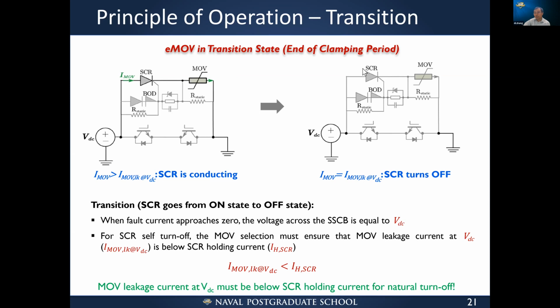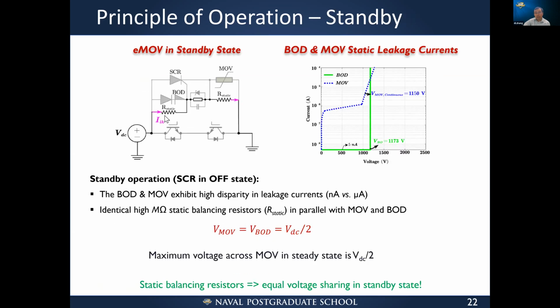So when the thyristor is turned off, the voltage sharing between the thyristors and the MOVs will be determined by the static voltage divider resistance. We just pick the values here so we can control the voltage sharing across the SCR and the MOV. For easy design, we keep it simple, half and half. That's why we want to pick MOVs that can withstand, instead of 1 kilovolt or 2 kilovolts, 1 kilovolt continuously. Okay.